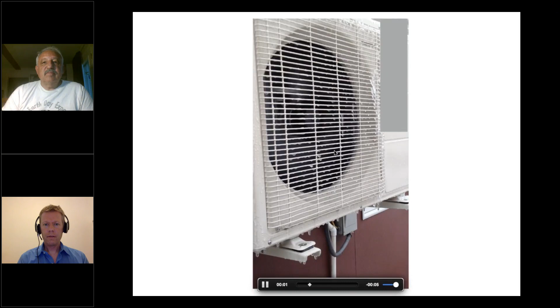That was a little video. I don't know if you could hear it or not, but there was a loud clickety-clackety sound because the outdoor unit fan blades were contacting ice that had built up on the outdoor frame. And this was an interesting case. This happens once every few years around here, where we get snow and then it's still cold but sunny. And so the sun melts the snow that's on top of the outdoor unit, and that snow melts and starts dripping down over the face, the front and the back of the outdoor unit. And if it's cold enough, it will start refreezing.